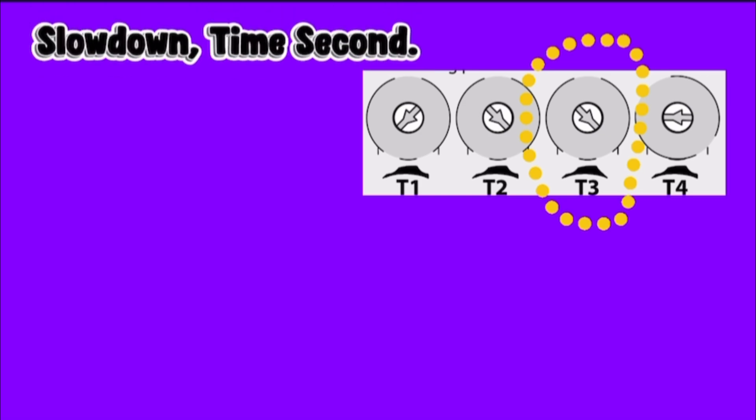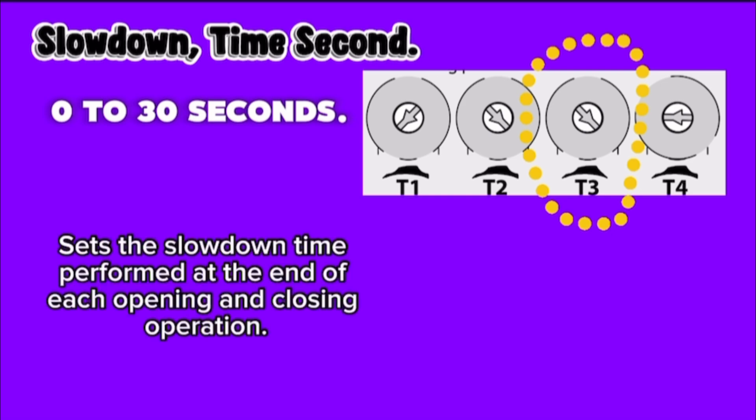T3, slowdown time in seconds. The time is 0 to 30 seconds. Sets the slowdown time performed at the end of each opening and closing operation. Zero means slowdown is disabled.